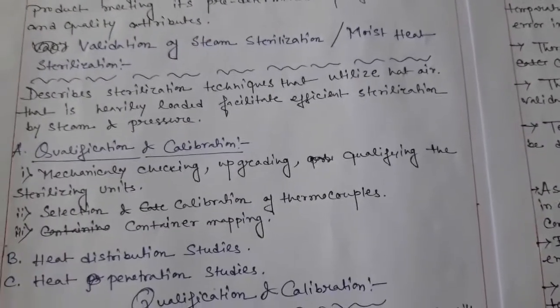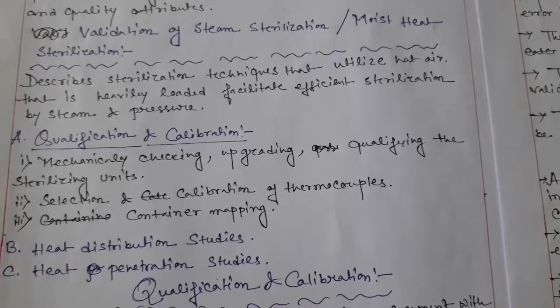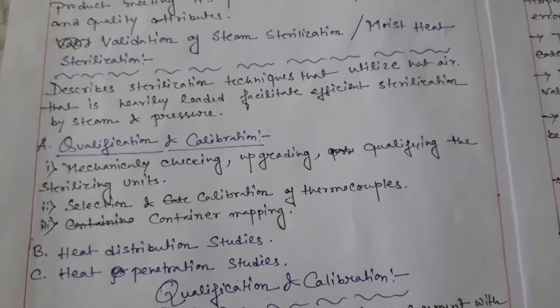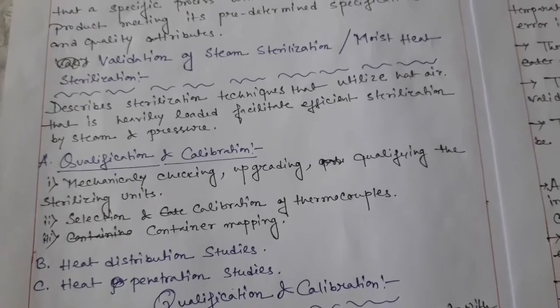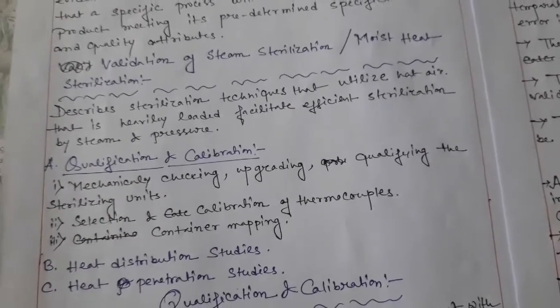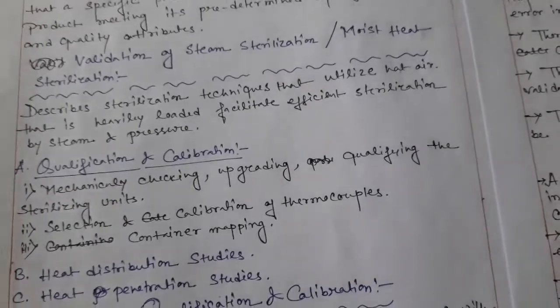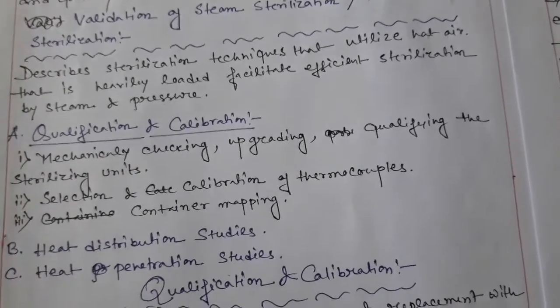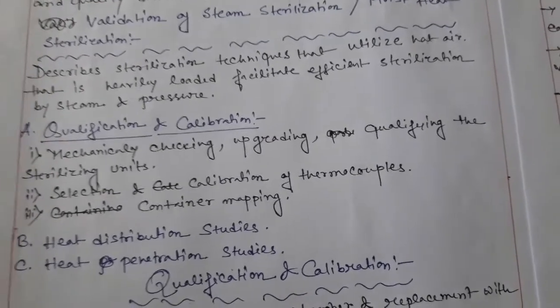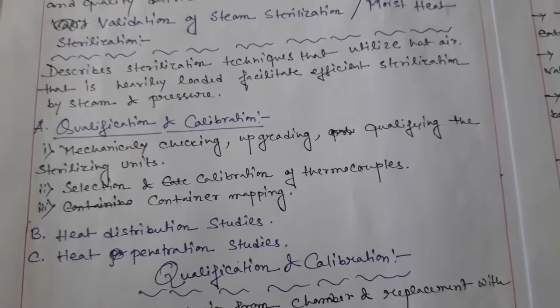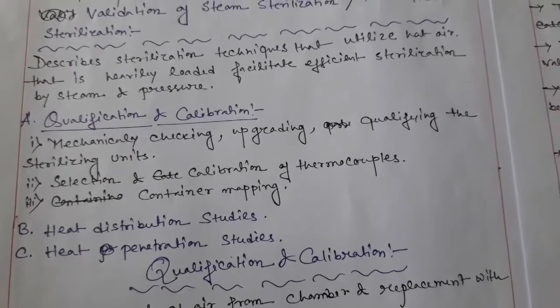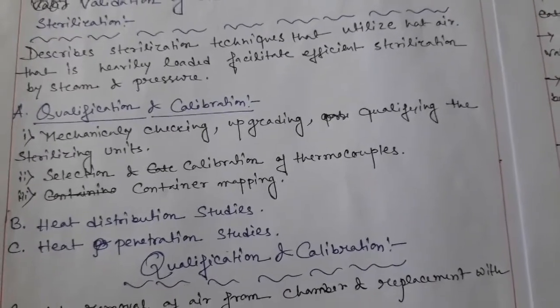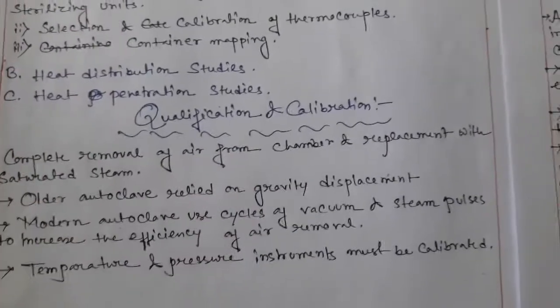The first point of autoclave validation is qualification and calibration. Qualification means how much quality the machine has, and calibration means how you calibrate the machine — that means making it error-free. There are three sub-points: mechanically checking and upgrading, qualifying the sterilizing units; second, selection and calibration of thermocouples; and third, container mapping.